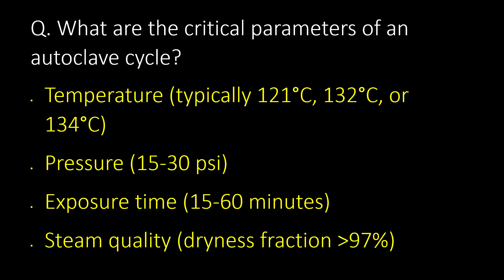What are the critical parameters of an autoclave cycle? First, temperature — typically 121°C, 132°C, or 134°C. Second, pressure — 15 to 30 psi. Third, exposure time — 15 to 60 minutes. And fourth, steam quality — dryness fraction greater than 97%.